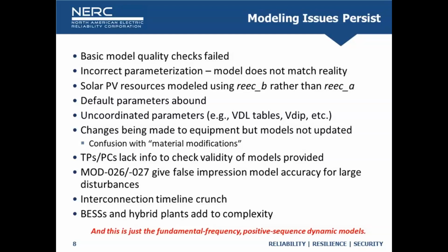The biggest one is incorrect parameterization. The models do not match reality—reality being the actual installed equipment out there in the field. We can compare that very easily with things like the NERC alert data, where the facility tells us exactly what they do, and you look at the model and it does something completely different. Things like momentary cessation versus current injection, or different set points, things like that. That second bullet is probably the biggest challenge we have.